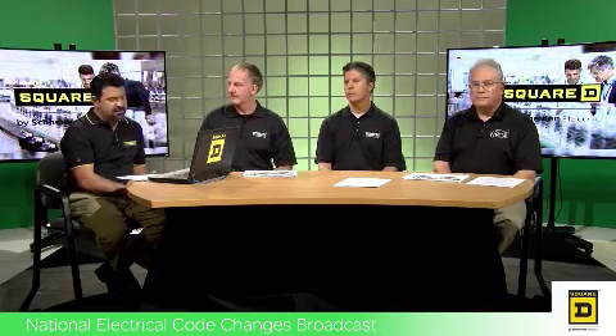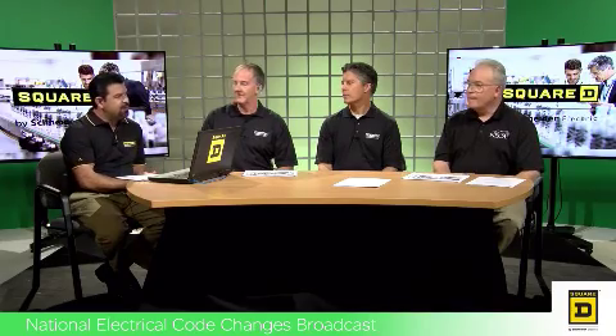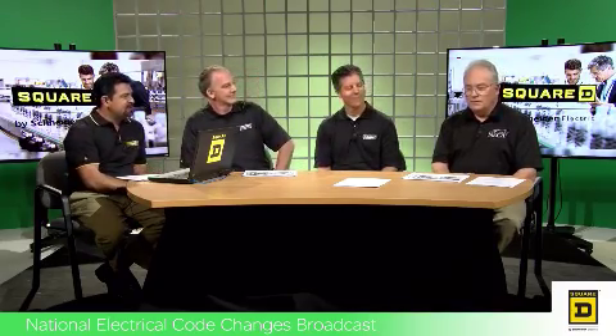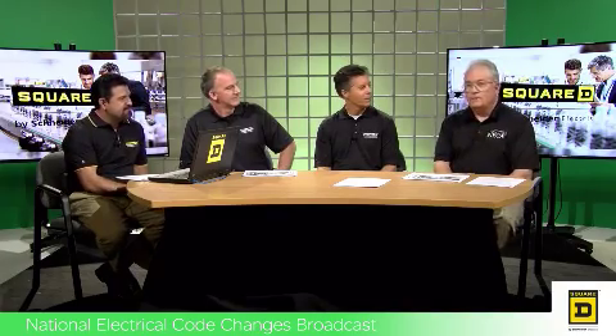So moving into a few other areas that can see the same type of arcing hazard. Great. Thank you, Alan. So this is an interesting topic. Mike, on Section 210.71, meeting room receptacle outlets, can you shed some light on that? Very good, sure, Phil. It's nice to see Code Panel 2 act favorably to include these new requirements for meeting rooms. When we consider abuse of cords and the way portable power taps have been used in meeting spaces, this change seems long overdue, in my opinion.